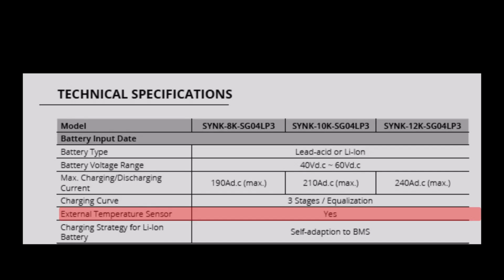The temperature sensor is used to monitor ambient temperature, to manage the internal cooling for safety and efficiency, and the maximum power point is also found using, among other things, the temperature. The charging strategy is the inverter adapts to the battery management system. Every lithium-ion battery has its own internal battery management system where it adapts to the volts and the amps and so on. And the inverter has a look at this data and adapts to it so that the battery is charged efficiently.